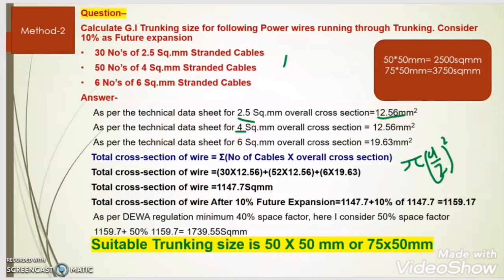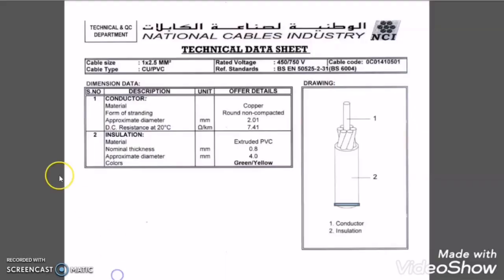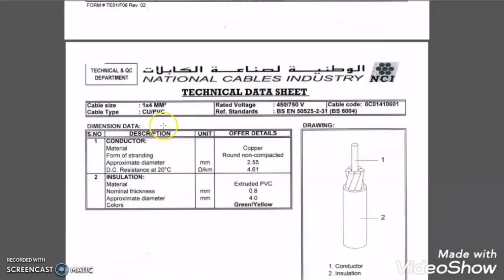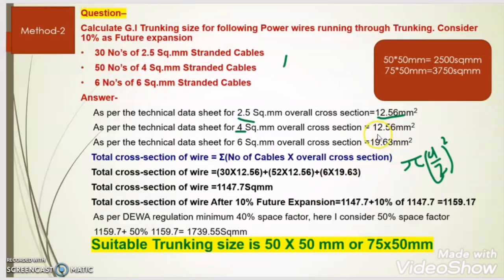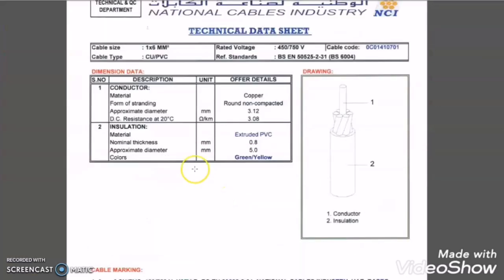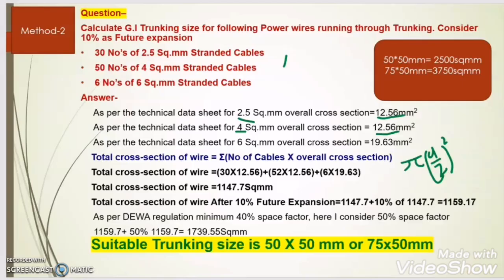For the 4mm wire, the overall diameter is also 4mm, so the cross section area is also 12.56 sq mm. For the single-core 6mm wire, the overall diameter is 5mm. Using the same formula, the cross section area comes to 19.63 sq mm.